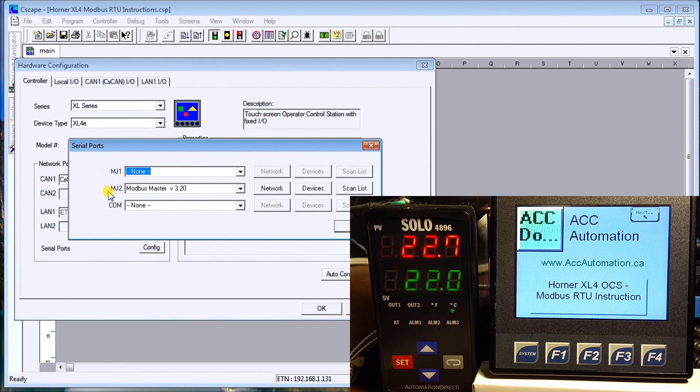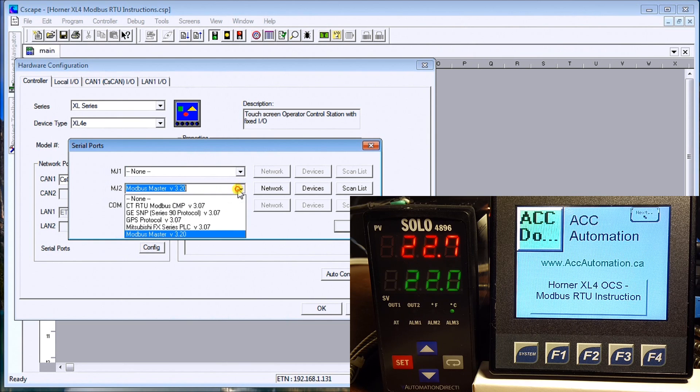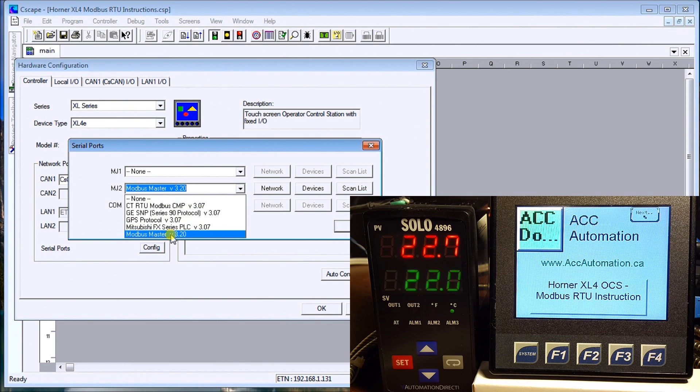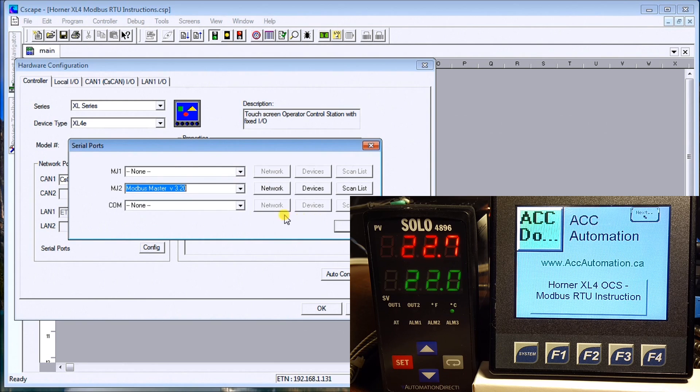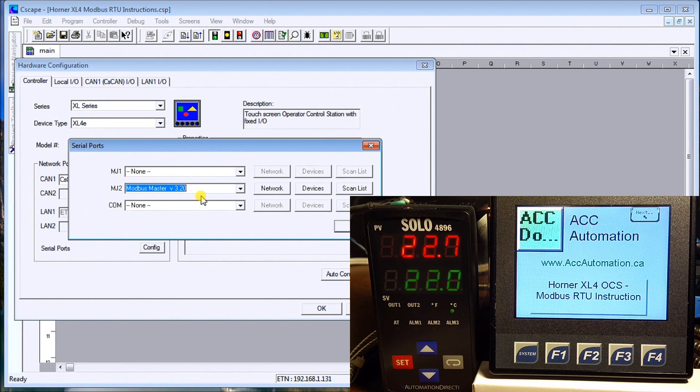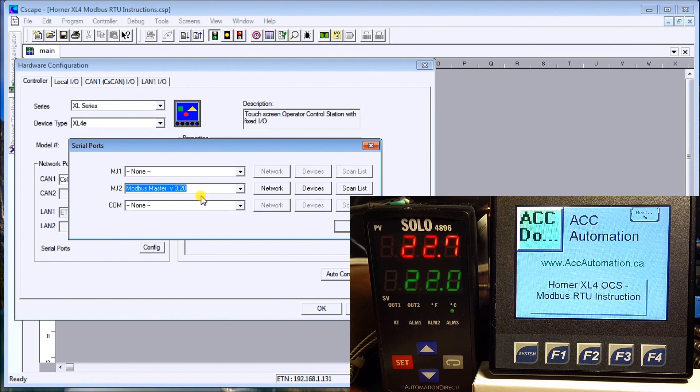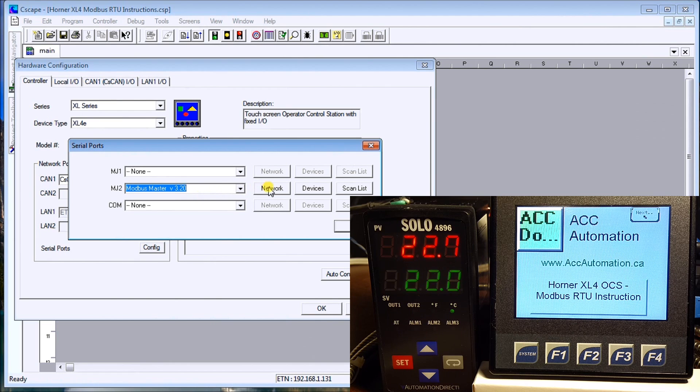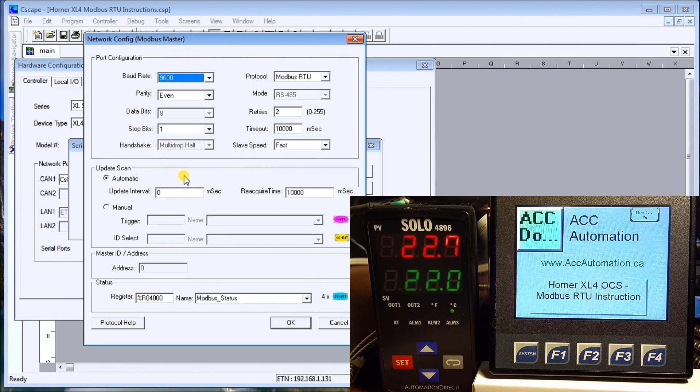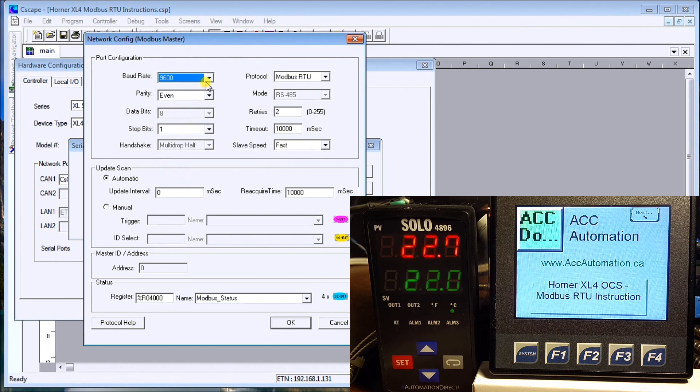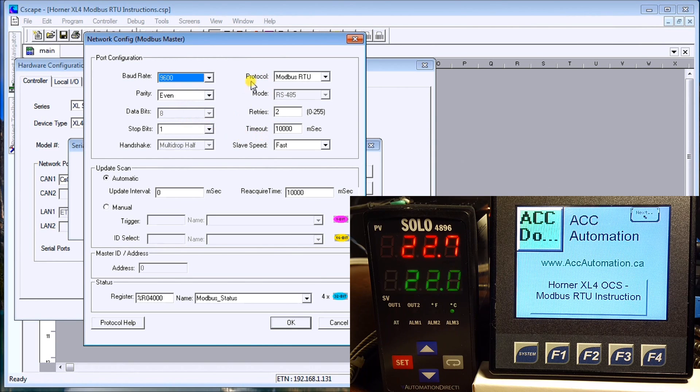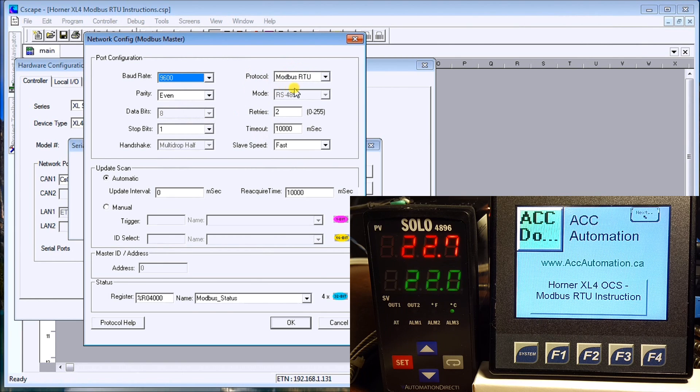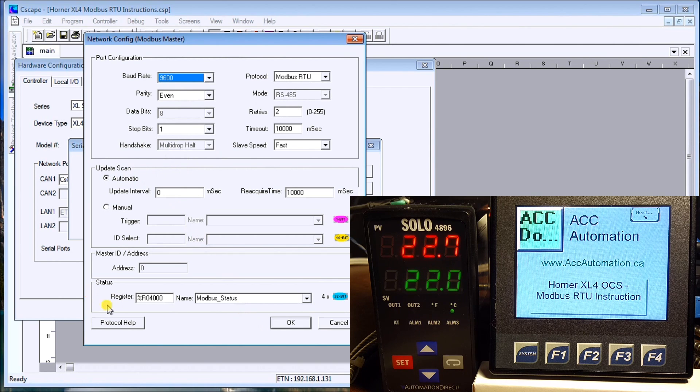It's the MJ2 as you saw in the wiring diagram. The first thing we want to do is select the Modbus Master because this is the communication protocol. All the instructions are going to come from our Horner into the SOLO and back again. Then we hit Network, and under here these are the settings that we use, the same as what we just set for the SOLO: 9600, even, 8-1. We have to make sure that protocol is Modbus RTU.